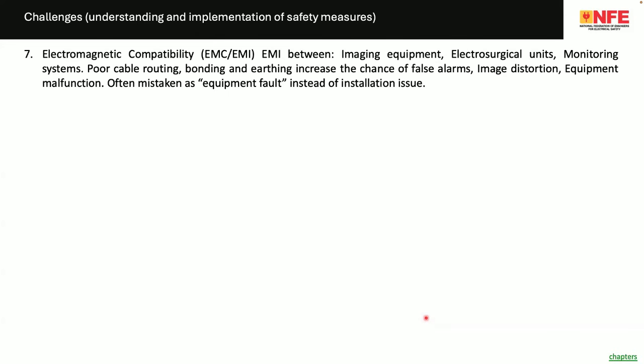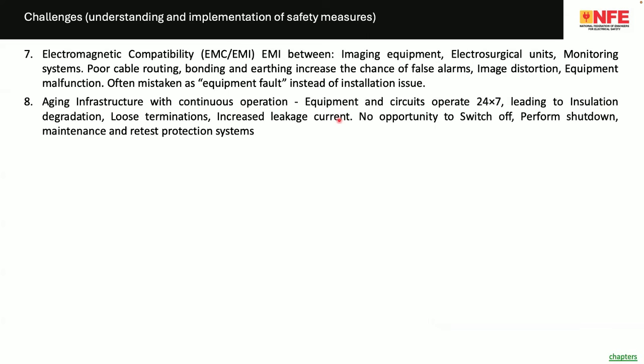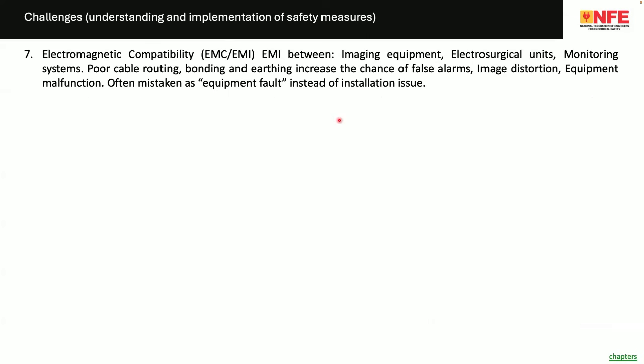Sometimes erroneous errors or erroneous results are coming on the screen. Sometimes other equipment create a problem. So these are actually EMI problems. So every electrical biomedical equipment should be installed in such a way that the EMI problems are handled very much, so that operation of one equipment is not creating a problem to the nearby equipment or to the patient. And these are not equipment fault.